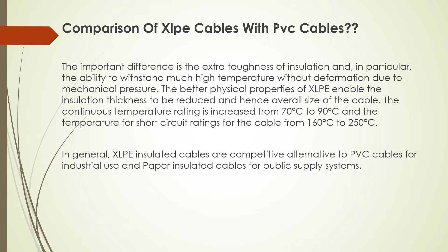The continuous temperature rating is increased from 70 degree to 90 degree and temperature for short circuit rating for the cable from 160 to 250 degrees centigrade. In general, XLPE insulated cables are a competitive alternative to PVC cable for industrial use and paper insulated cable for public supply systems.